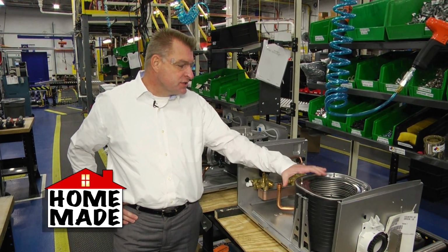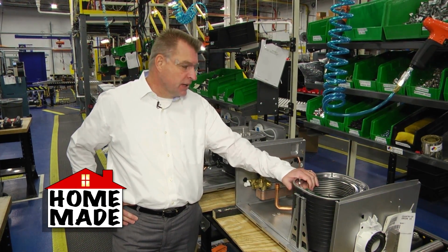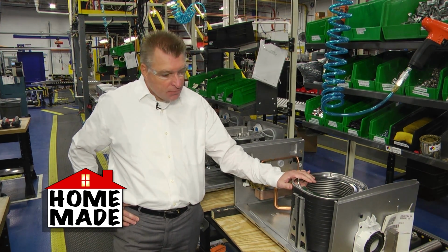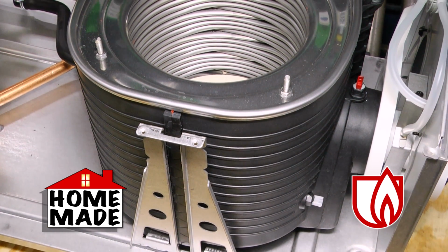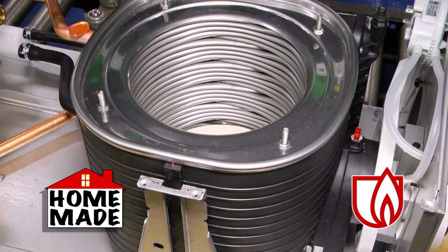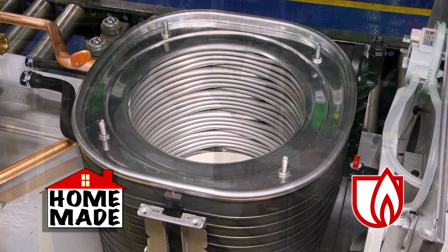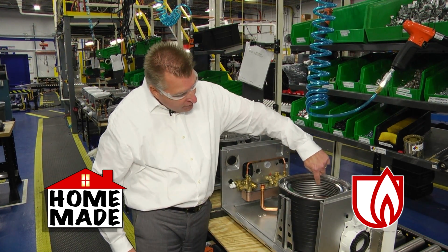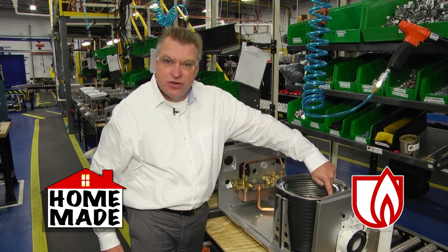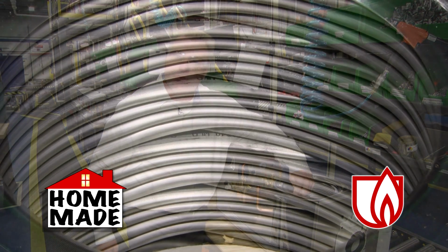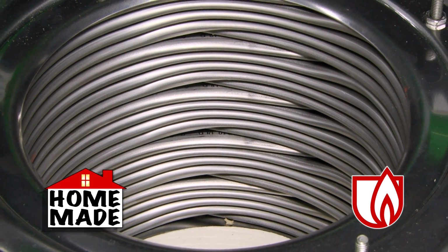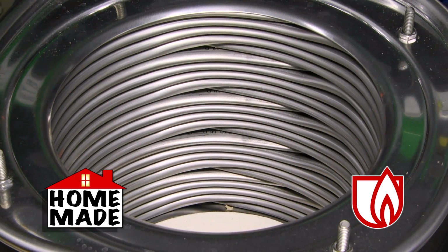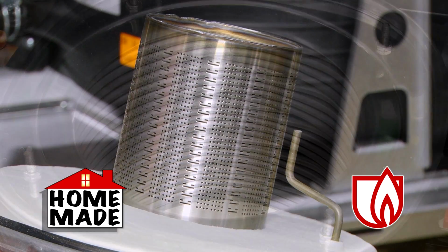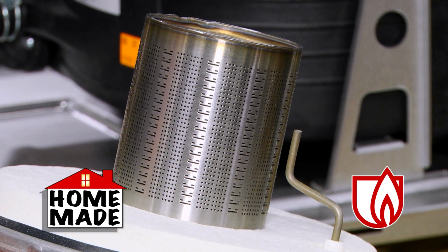What we have here, this is a stainless steel heat exchanger. This is the lifeblood of this particular boiler unit. Overall, it's a stainless steel, 316L heat exchanger. The way this works is overall you have the coils inside the heat exchanger. Water is actually flowing through those coils provided by a pump. Within this coil, basically you would put a burner, which mixes the gas with air that provides the heat source to heat the water up.